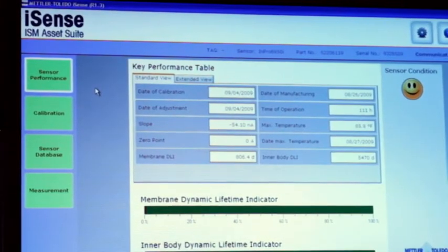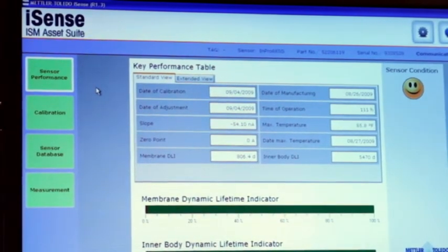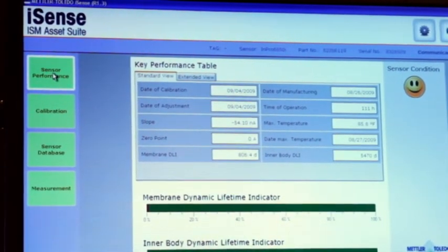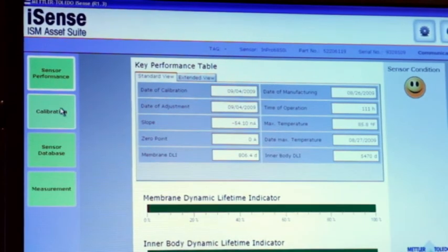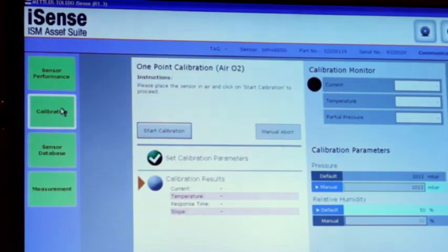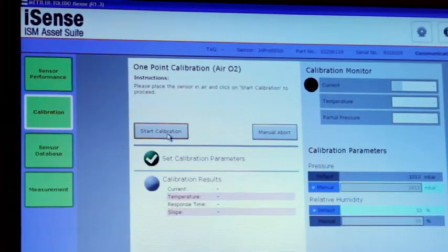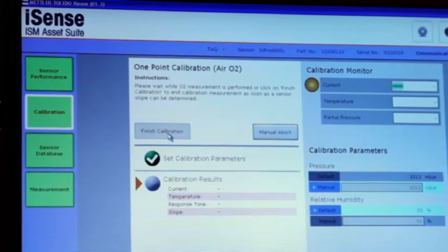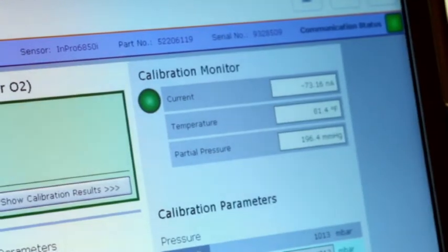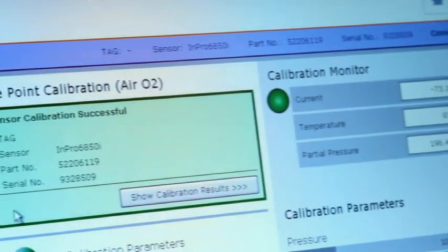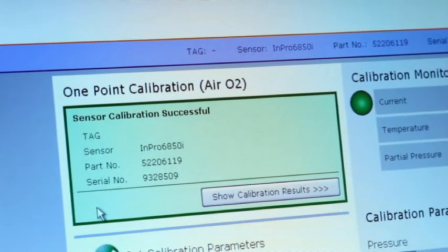After the sensor has been polarized, calibration is necessary. Using iSense, this can be performed easily in a lab environment. Because the amperometric sensors are highly linear from 0 to 100% oxygen, it is sufficient to perform a one-point calibration in air. The calibration itself is very fast and straightforward.